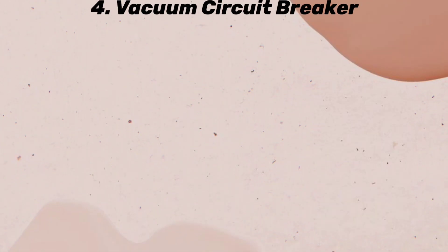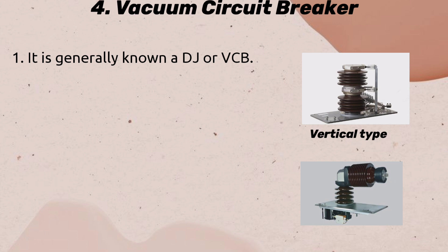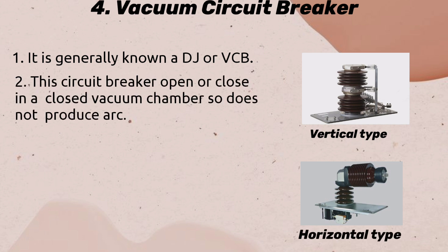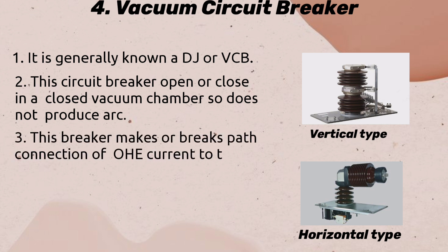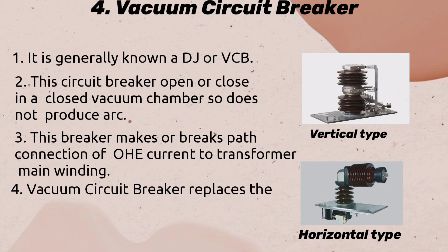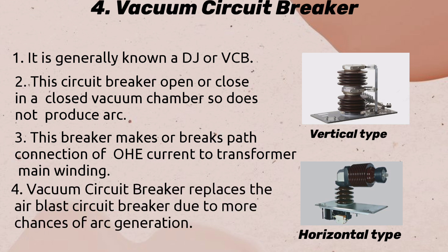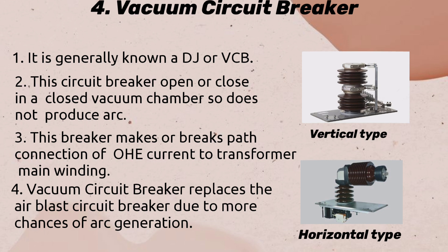Vacuum Circuit Breaker: It is generally known as DJ or VCB. This circuit breaker opens or closes in a closed vacuum chamber, so it does not produce an arc. This breaker makes or breaks the path connection of OHE current to the transformer main winding. The Vacuum Circuit Breaker replaces the air blast circuit breaker due to more chances of arc generation in the latter.